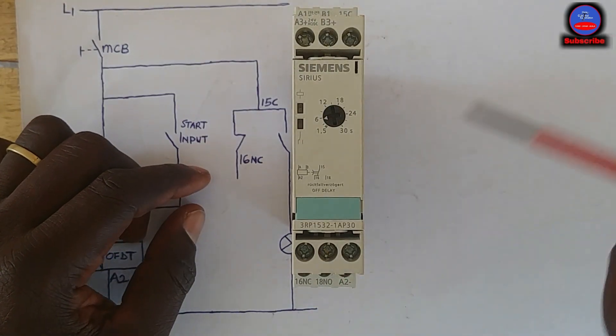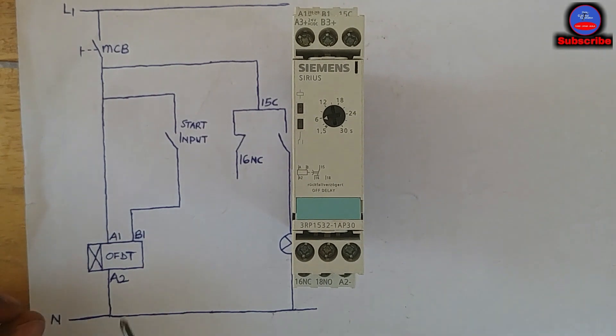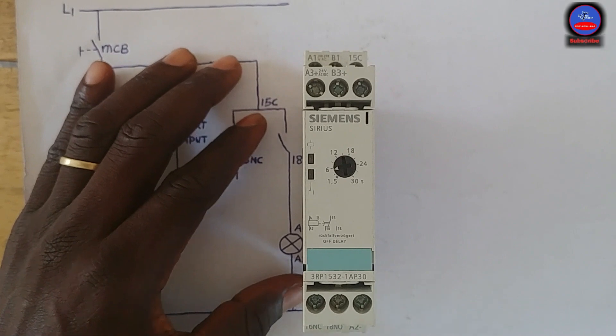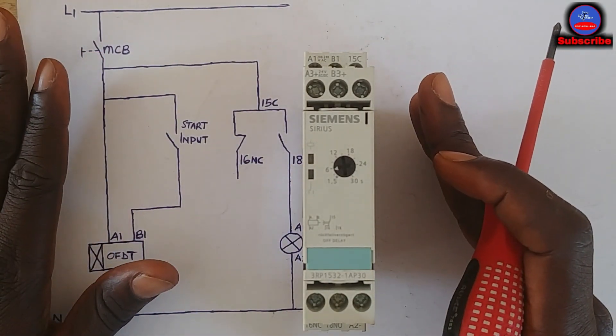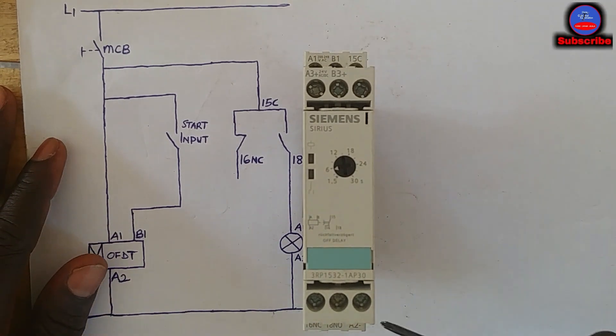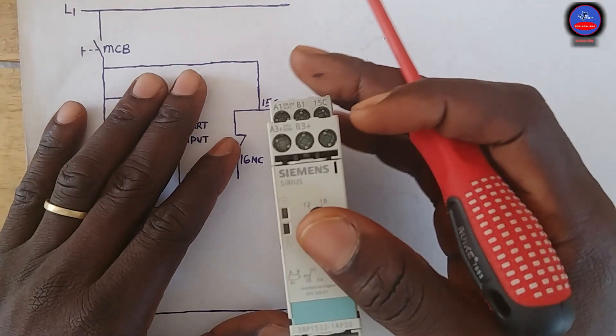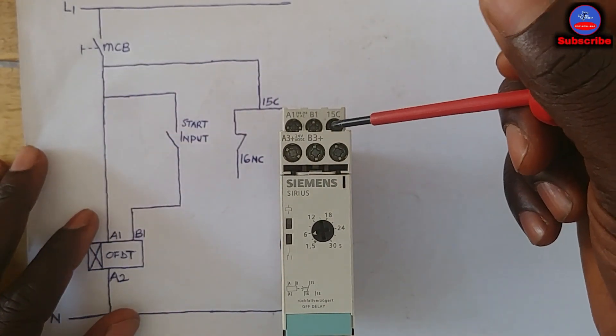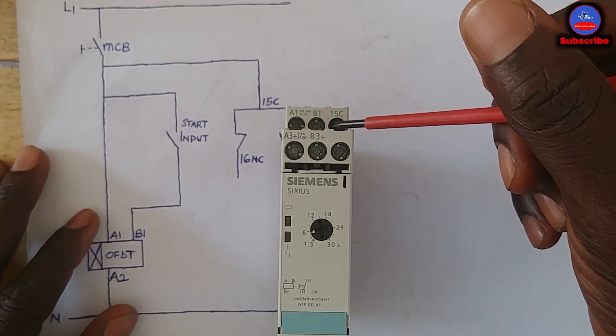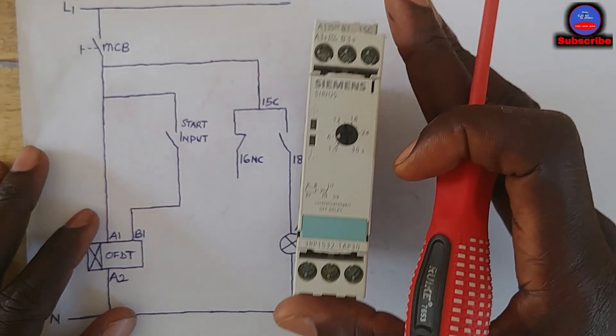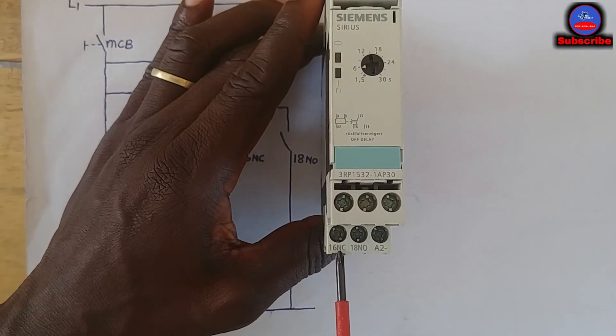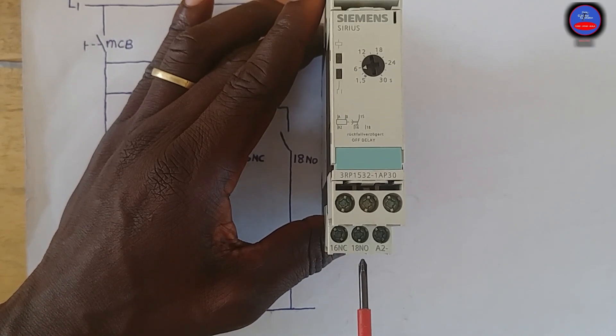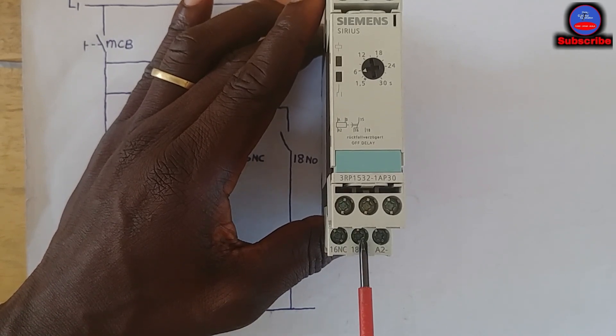For AC, the coil terminals are A1 and A2. Since we are using this timer on AC, we are going to use A1 and A2. For the contact terminals: 15C is the common terminal, 16NC is the normally closed terminal, and 18NO is the normally open terminal.